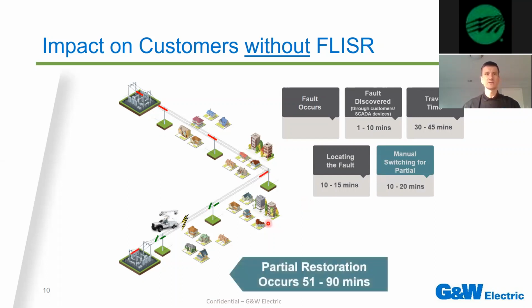The partial restoration here means that we are opening upstream and downstream of the fault to isolate the fault. We're closing in the tie, if we have the luxury of having a tie, and if the substation in the north has the capacity to pick up those loads down here in the south. And then as a last step, close the substation breaker back in. So now we have the fault isolated here, and we have a partial restoration, as I call it, in a matter of an hour to an hour and a half, right? So this is probably a good optimistic estimate.